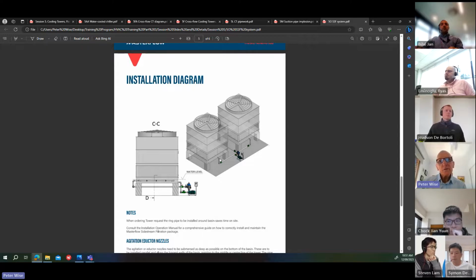You'll find on most jobs, there's another picture here that gives you an idea of these. If you can see those parts around the basin, they're the eductor nozzles, which send a jet of water into the basin and stir up the dirt, which is then returned to the filter. This is pretty common now in all cooling tower basins. You'll find that they're going in.